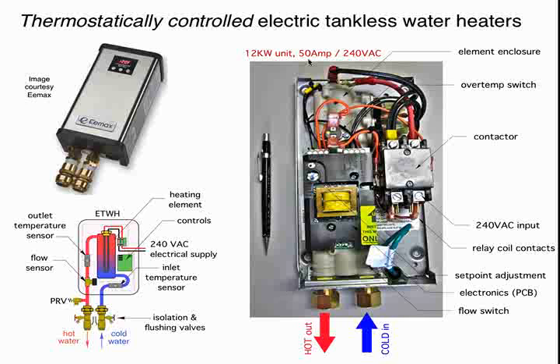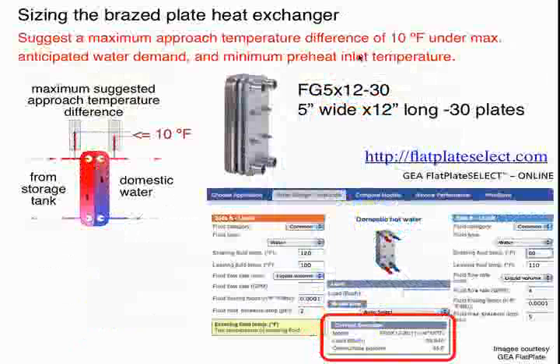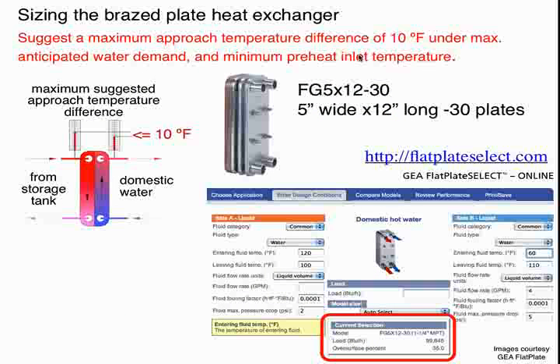You can see a 12 kW unit here, 12 kilowatts. It's not a very large unit. It's maybe 10 inches tall, 5 inches wide. You can hold it in your hand, but when it's operating, it's 50 amps at 240 volts. So it's a pretty strong demand. Remember, you're heating the water instantly, so there's a lot of power flowing into this.